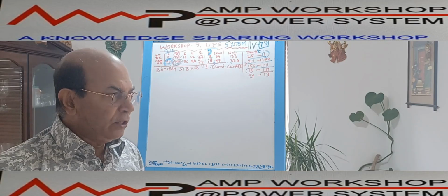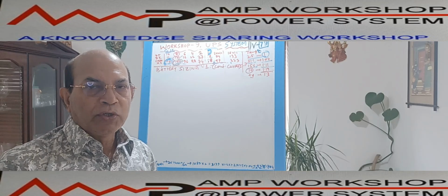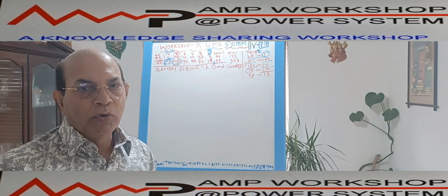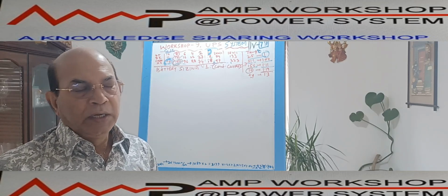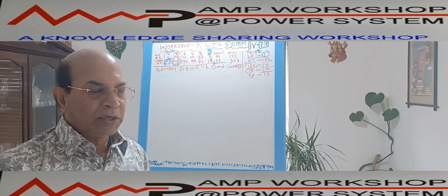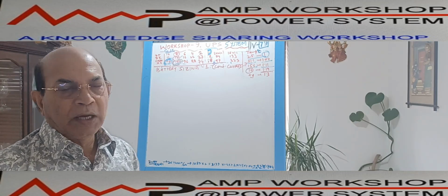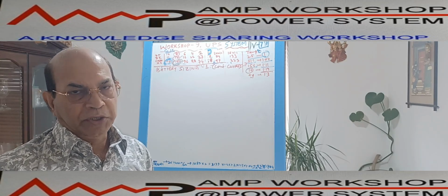So in this video, video number 79, we are going to discuss battery sizing based on a constant load or constant current at the UPS, the UPS current being maintained constant over a period. When we consider the period, we will discuss in detail how the period is to be selected. So let's start the sizing calculation for the constant current UPS battery.